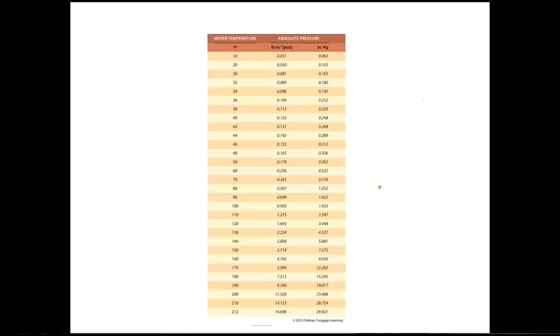And we have these charts for refrigerant as well. But let's look at this. This is atmospheric pressure down here at the bottom, 14.7 psi. At atmospheric pressure, water will change state at 212 degrees. Now, let's say we reduce that atmospheric pressure and we put the water into somewhat of a vacuum, we can change the state of that water at 70 degrees Fahrenheit. And the same thing happens if you increase the pressure, and it increases the temperature that the water changes state. We'll get into this again when we get into the refrigeration cycle. This will start to make some more sense.